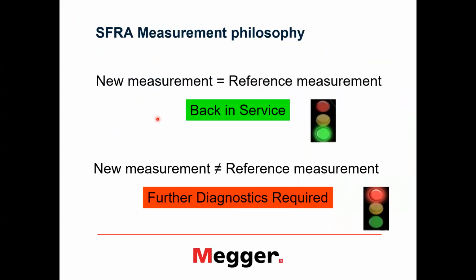The philosophy of the measurement technology is also rather simple. If we have a new measurement and a reference measurement which we can compare, and they are the same or with insignificant differences, then everything is fine. We can put the transformer back in service.